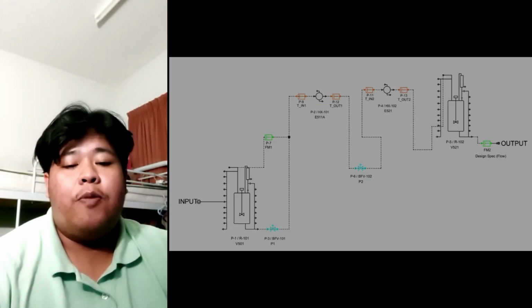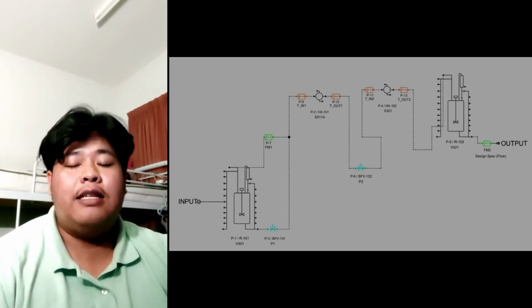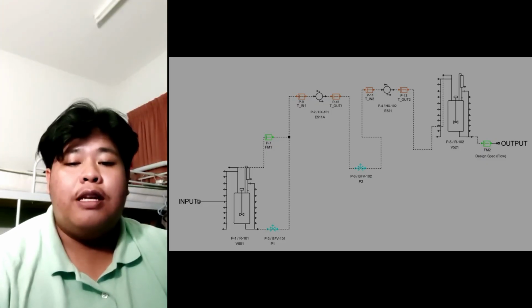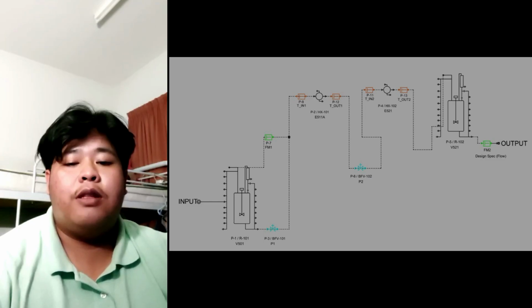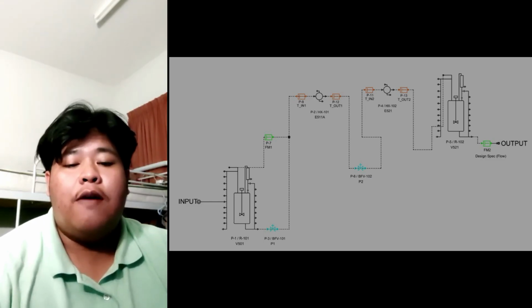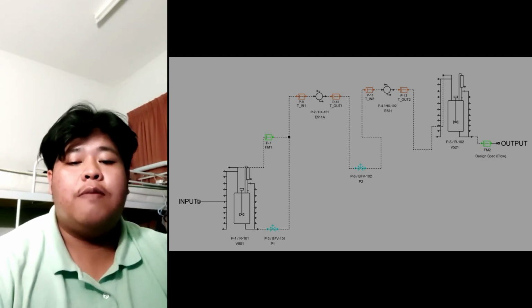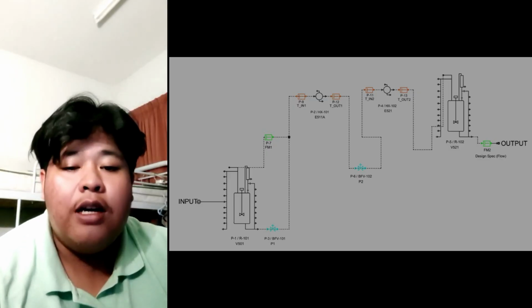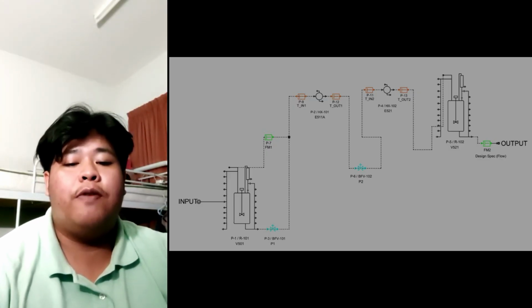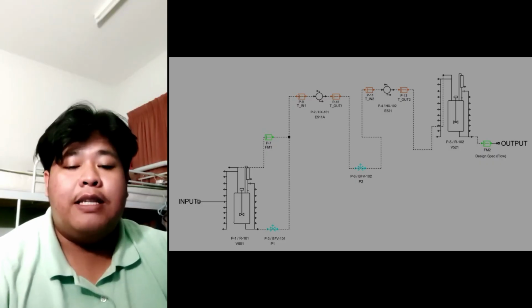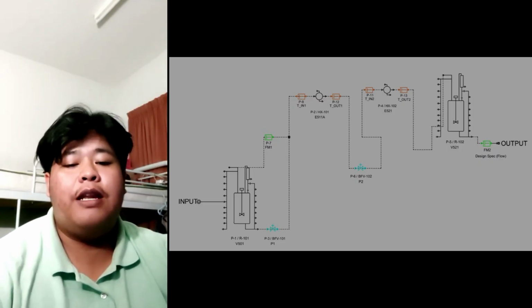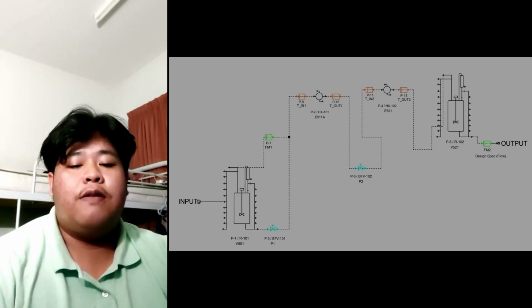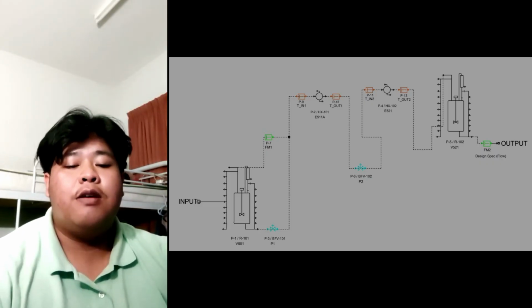By integrating this component into the SCADA system, we can monitor the differential pressure across these heat exchangers. If we see a pressure drop that doesn't match the flow rate at FM1 or FM2, the system alerts us to early fouling or blockage before the equipment fails.